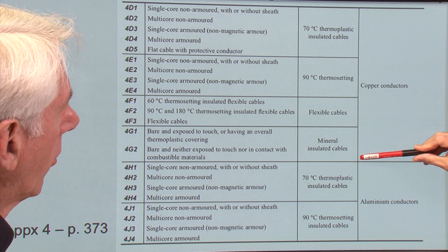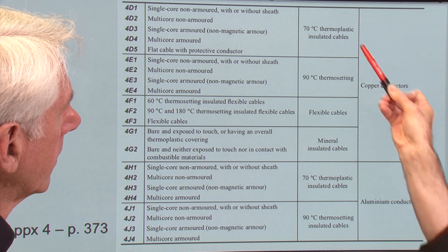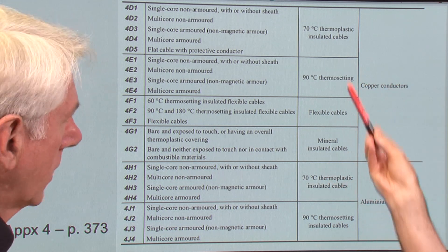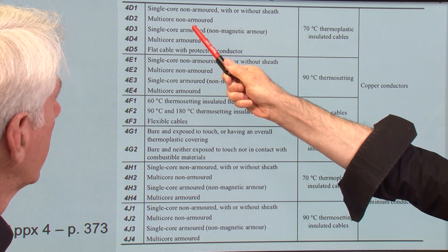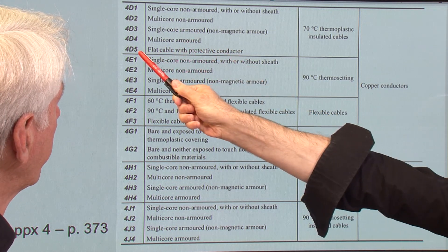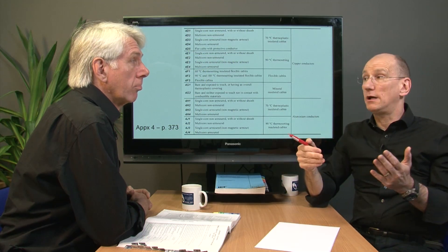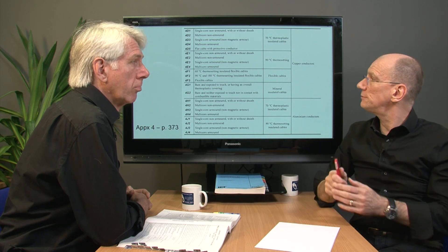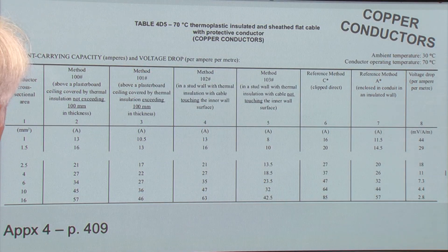We're not doing mineral insulated, we're not doing flexible. We've got a choice of thermosetting or thermoplastic, but from the question it was 70 degree thermoplastic. So we've eliminated those and we're concentrating on just a few options. It was flat twin, so we need to go to table 4D5. We can thumb through the pages, which can be quite time consuming, but if you've already been there we can turn straight to page 409. A useful tip is to put the page number on the flag tag so you can go straight to it.